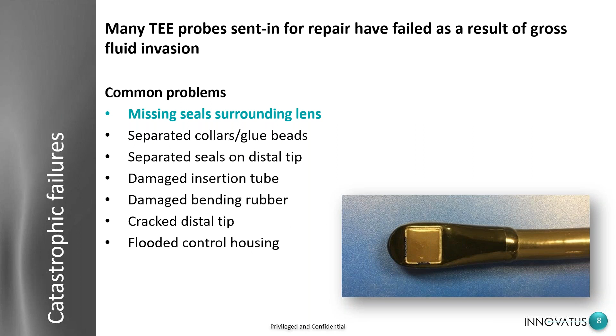So if we look at how this occurs, first of all, we have missing seals surrounding the lens. If we look at this particular probe here, you can see that the sealant around the lens is starting to go in these areas. We can replace that sealant. Separated collars or glue beads. This is where the insertion tube up here meets the bending rubber. There is a collar along with a glue bead that seals that up, and you can see that the glue bead is starting to create a gap. And that's where we can get that gross fluid invasion.